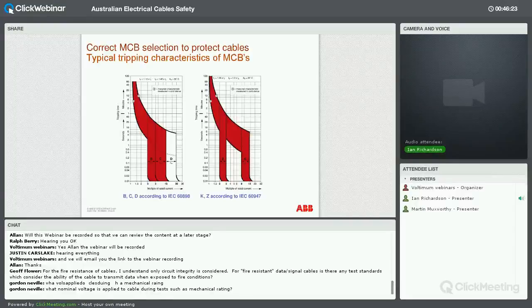So here's a couple of tripping curves of miniature circuit breakers. I would suggest most of you have probably seen the ones on the left-hand side. Most commonly people will tend to use a C-curve breaker, but there are also the Bs and the Ds according to the 60898 standard. A couple of other curves that you may have seen are the K curve and the Z curve, which are defined in the 60947 standard. So there are miniature breakers that can have any one of these 5 curves. Not all of the miniature circuit breaker manufacturers have them available. The most common ones are the B, C and D, but there's a couple of companies, ABB included, that have the Z curve and the K curve in addition.